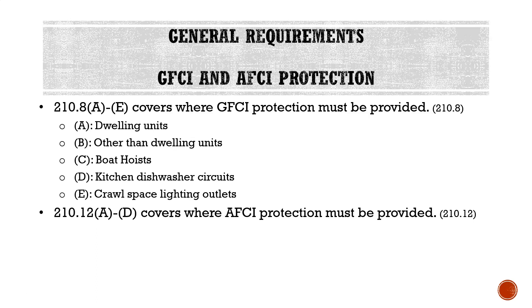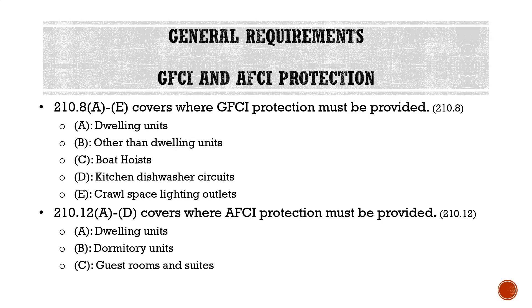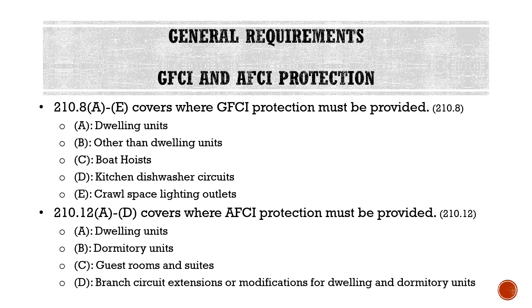Section 210.12A through D covers where AFCI protection must be provided — same concept as 210.8 but for AFCI protection. Part A covers dwelling units, Part B covers dormitory units, Part C covers guest rooms and suites, and Part D covers branch circuit extensions or modifications for dwelling and dormitory units — meaning where we are modifying or adding on to an existing circuit in those locations.